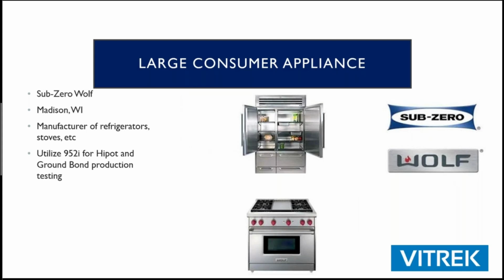So, like what I was saying before, we also use our products where it's going to be high power applications. Refrigeration and heating, you're going to have big turn-on surges with those compressors. Electrical heating elements, although they are purely resistive, are going to have large power demands. In those situations, sometimes we'll use a product like the 952 that has a little bit more power, a little bit higher ground bond current to make sure that you can properly test higher power devices.